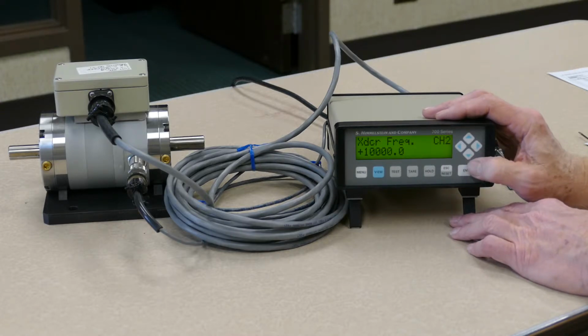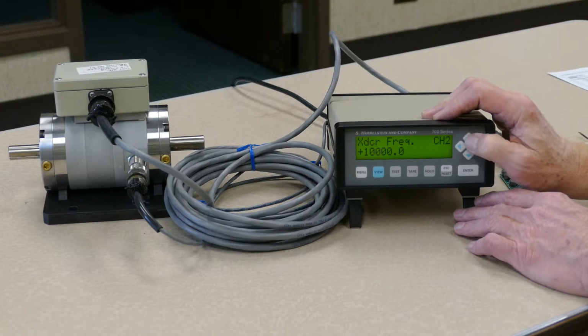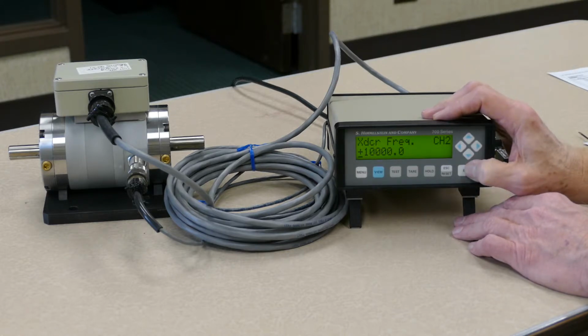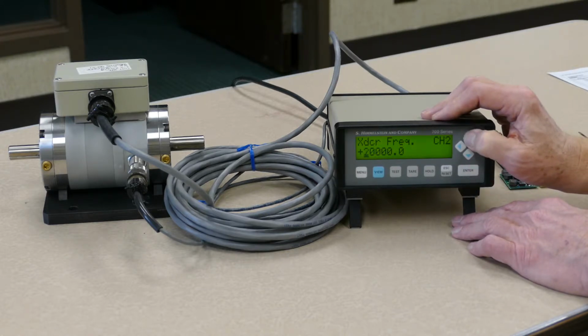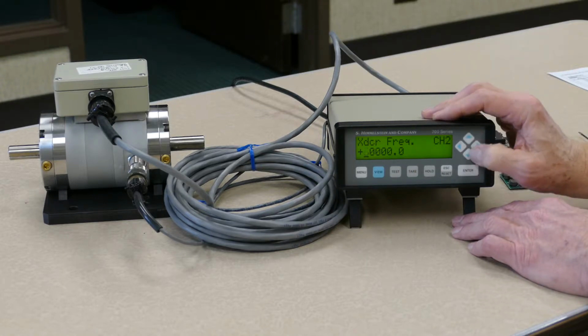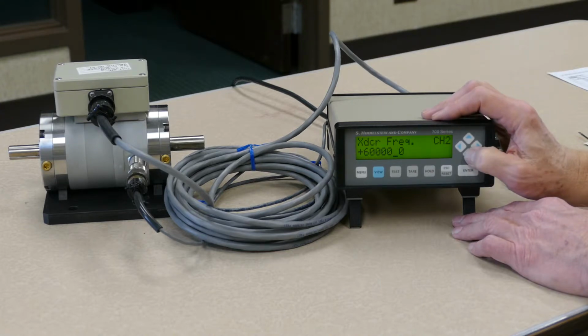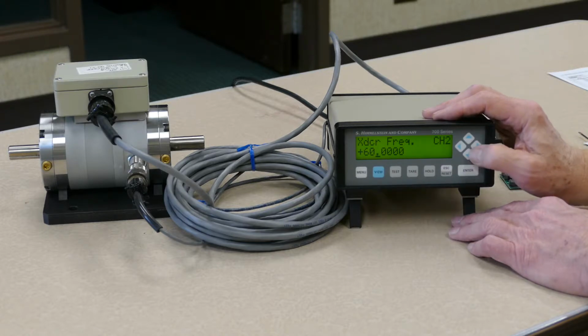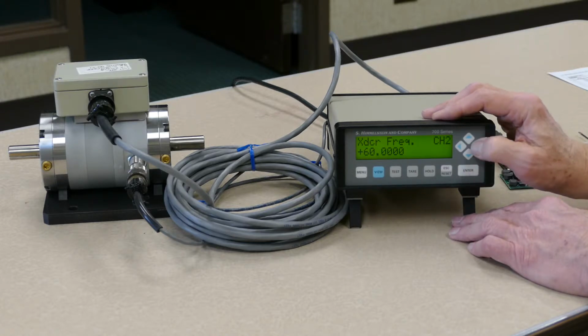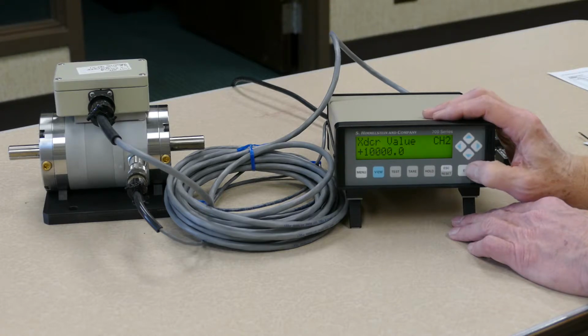The next question is the transducer frequency. We are using a 60-tooth gear to measure the speed. So we are going to enter in for the transducer frequency the value of 60. So again, hit the enter key. Change the first digit to be a 6. Move the cursor to the decimal point, and with the down arrow, move the decimal point back to the left until it reads 60.00. Hit the enter key to accept, and the right arrow again.